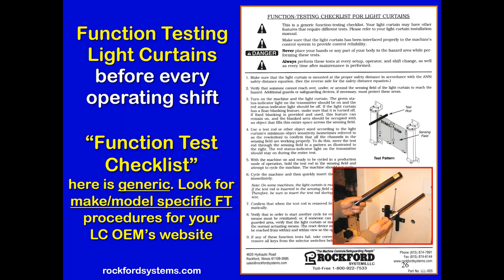The only place you'd use a generic is where you have a light curtain manufacturer that's no longer around. So you have to start with something to develop your own procedures. Notice the photograph with the two black sticks being held by those two hands there. Those are test rods for light curtains. Most light curtains require two test rods, a fat one and a skinny one. And their diameter is very specific. It's not like one size fits all.